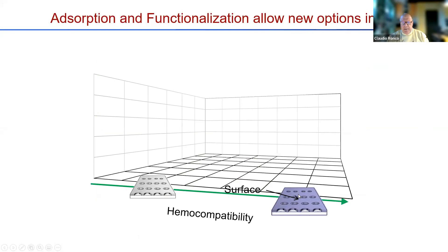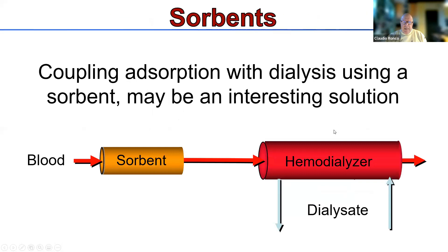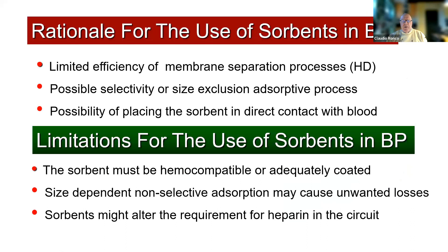Originally we added to the membrane mostly hemocompatibility, modified the surface, then we modified porosity to change flux. And today we modify the surface with bioproperties and the capacity of adsorbing. Coupling adsorption with dialysis is a good idea. But instead of using the membrane for this purpose — which can be maximally one or two square meters — we can use sorbent devices that may exploit up to 20,000 square meters of possible adsorbing surface.